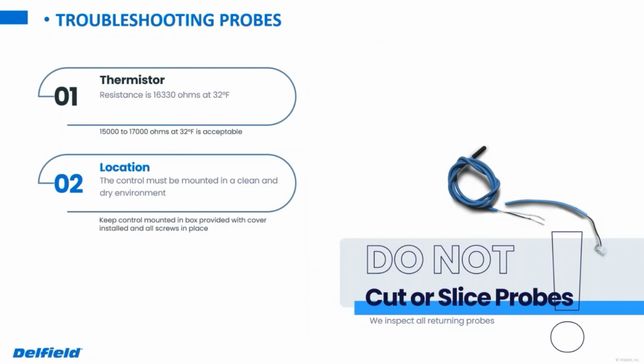Don't make it your first, because probes operate off of resistance. So anytime you make a cut and a splice, you are affecting that resistance to some degree, no matter how good of a job you do. So just make this your last resort, not the go-to. In the event that you do need to cut and splice a probe, you would cut it inside of the cabinet, cut the old probe off the existing wire, and then cut the new probe off and splice it into the original wiring. When you do this, in a perfect world, you'd solder your joint.